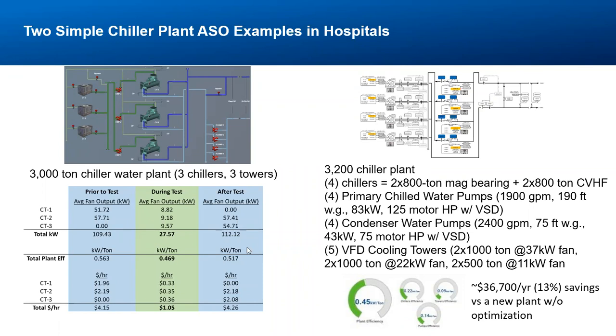The example on the right has one more chiller, a combination of mag-bearing chillers and some traditional centrifugal chillers, a variable primary system with variable speed condenser water pumps and cooling tower fans. In that example, we're on track for about 13% overall savings, which is just over $36,000 a year in that particular plant.